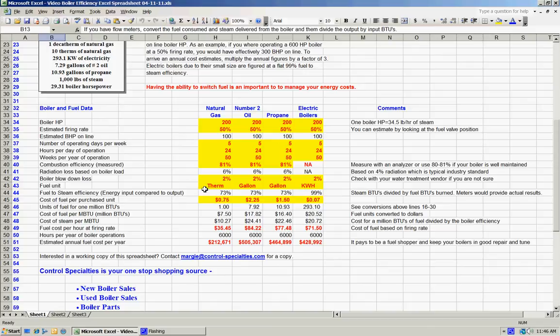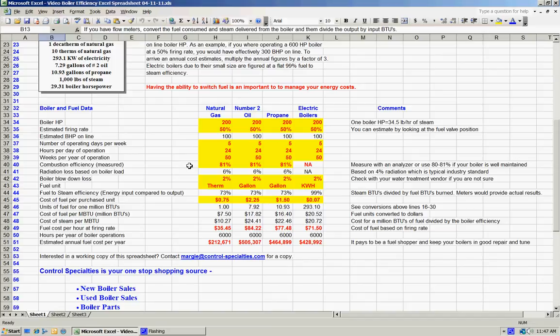If we follow the rest of the numbers down, we've filled in a bunch of data for you here. If we just drop down the line 40, I'll just comment on a few. Combustion efficiency is measured with a combustion analyzer. If you have access to one or your boiler service company can provide that information, they can give you a precise measurement of the combustion efficiency, which is how well you're converting fuel to energy and the amount of energy going up the stack. If you don't have a number, if you typically use about 80 to 81 percent for a boiler, which is well maintained, you're going to be pretty darn close.